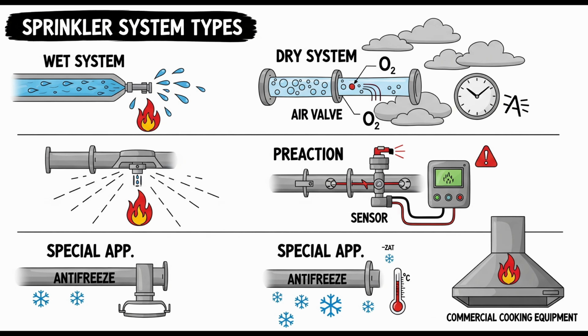If the hood design includes a listed fire damper installed right in the collar, then the sprinkler or nozzle must be located on the discharge side downstream of that damper and positioned so it won't physically interfere with the damper closing properly. Okay, protect the duct just downstream of the fire damper if one exists, and the plenum chambers themselves inside the hood. The plenum chamber, that open space inside the hood, usually above the filters where vapors collect before entering the duct, also needs protection. One sprinkler or nozzle is required, located centered, in plenum chambers that are 10 feet long or less. For chambers longer than 10 feet, two sprinklers or nozzles are required, evenly spaced, with a maximum distance of 10 feet between them. Targeting that main collection area for grease-laden vapors right inside the hood makes sense.